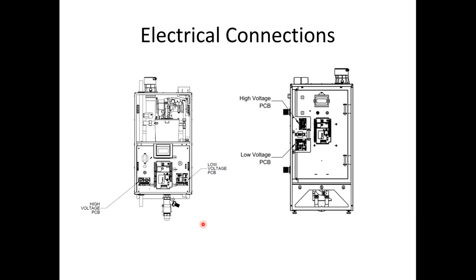So the electrical connections: the wall hung products are going to have, on the left-hand side of the boiler facing it, your high voltage PCB. Low voltage is going to be on the right-hand side. The floor-mounted 320 and 399 are going to have your connections right on top of one another, and this front panel door opens up.